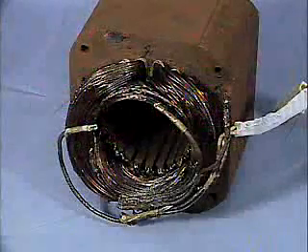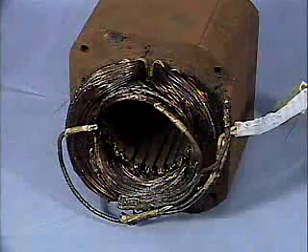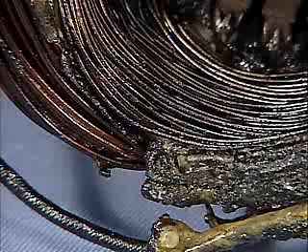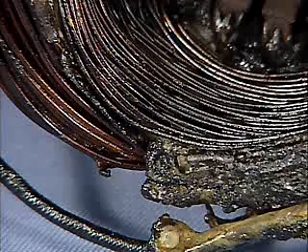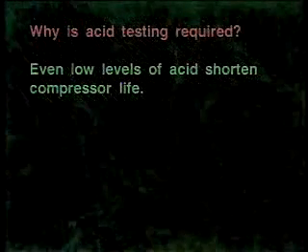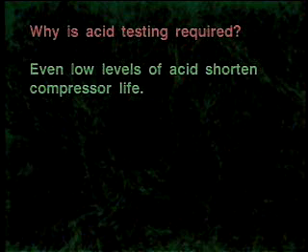Acid is damaging to the system and can cause internal corrosion and future compressor damage. Acid can etch the lacquer insulation off the compressor's motor windings, leading to compressor motor burnout. The more acid in the system, the faster the insulation is etched away, but even low levels of acid shorten compressor life. That's exactly why many times a retrofit compressor does not last as long as the original compressor.